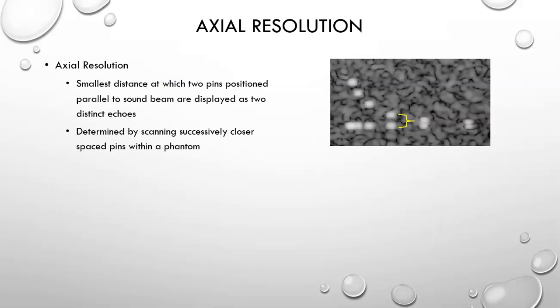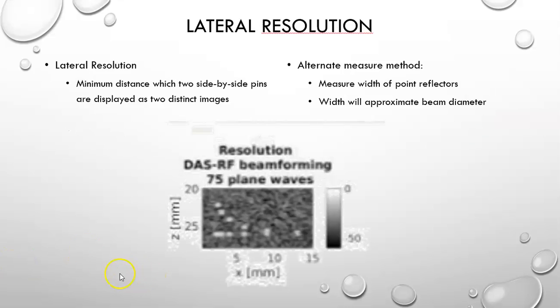To measure axial resolution, you simply look at the pins. The smallest pins that you can definitely separate apart tells you your axial resolution, and then you just pick up the manual that tells you how far apart those pins are, and that's your axial resolution. With lateral resolution, we do the same thing, but we do it side to side. So you would look at this and say, okay, the first point where I can see side to side with my lateral resolution is right in here. And you'd go look up in the book and find out how far apart these pins are.